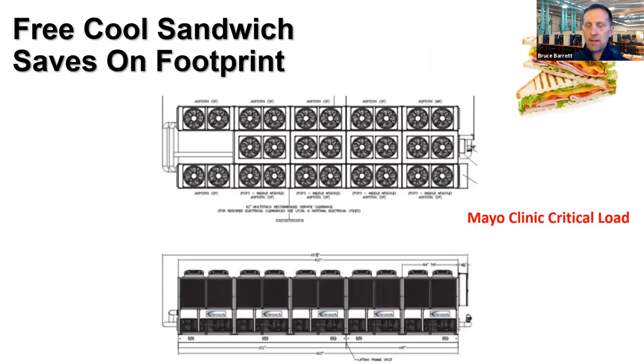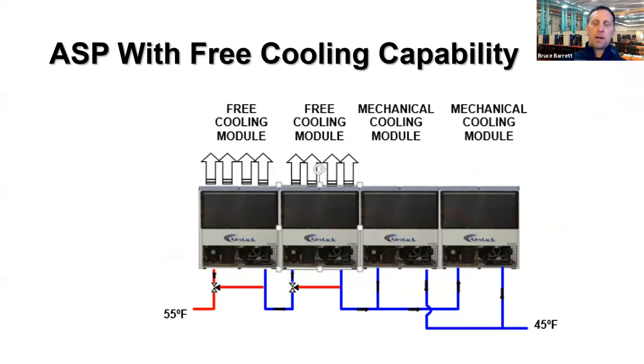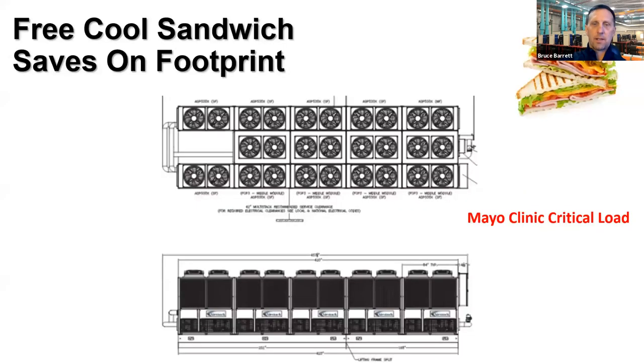We've done some really creative free cooling options in order to save footprint. So previous slide, we can stack a bunch of modules in a row. Our 30-ton modules can go back to back. So we can put a lot of free cools with mechanical modules, but our 60-ton modules get quite long. They go end to end. It might outreach the chiller yard ability to capture those. So we started thinking creatively about having a great amount of capacity with free cool in the smallest footprint.